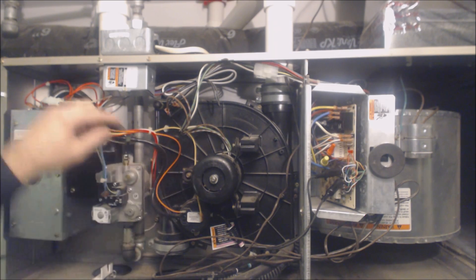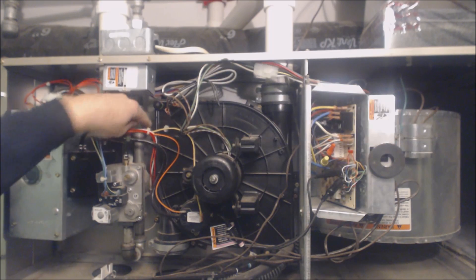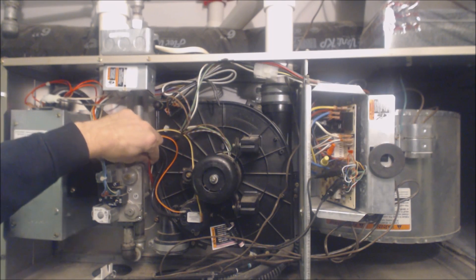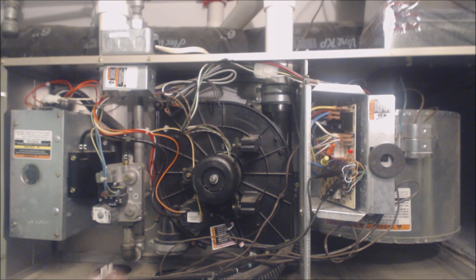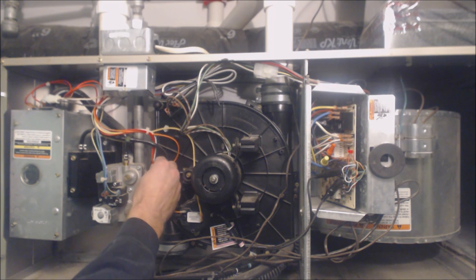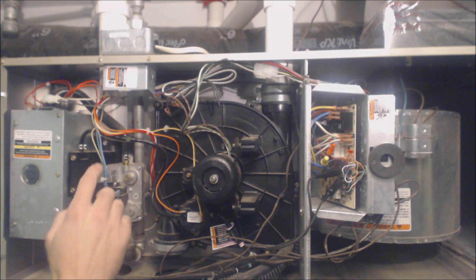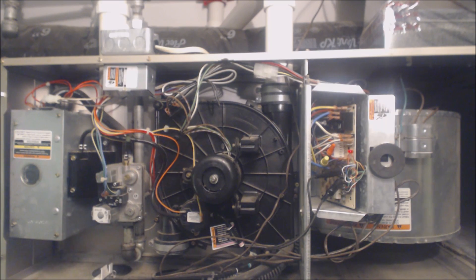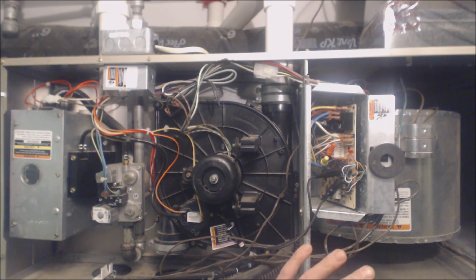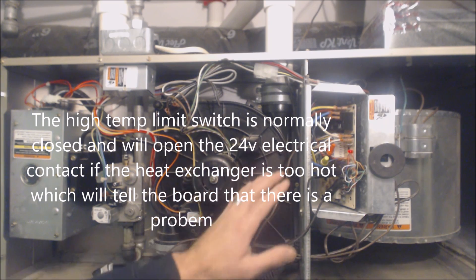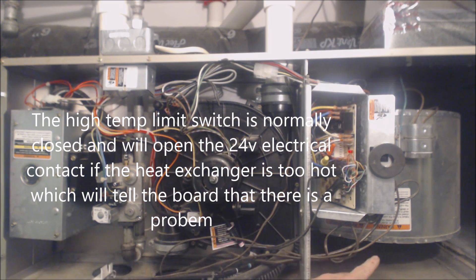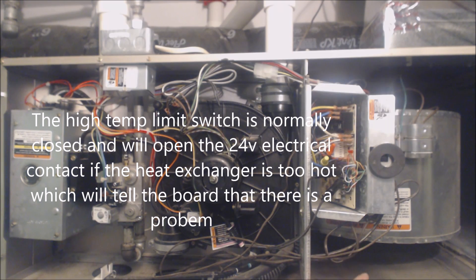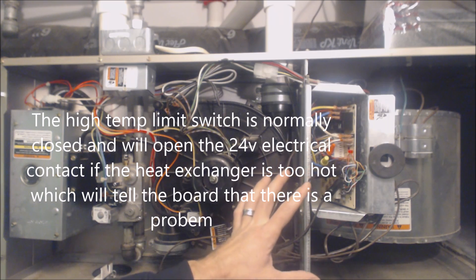Back here, you can't see it on this furnace, but back here connected to these red wires, you have a plenum switch. It's a high temperature thermodisc back here. What that's doing is if that were to ever heat up too much, then it will not even allow the furnace to turn on the sequence of operation. It'll turn the blower motor on typically and only for a period of time. But after that, it'll maybe lock out the system.